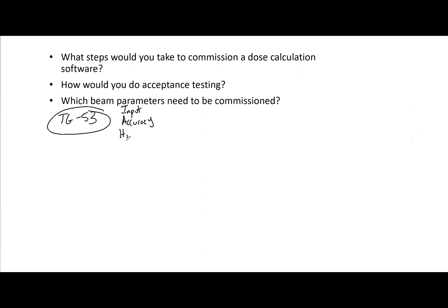You want to do this with water phantoms, and any type of anthropomorphic phantom is also good. Use a variety of plans — prostate, VMAT, SRS, SBRT, gating, any type of plans you could think of. You want to test all of those, and they are outlined in TG53. There's also much more in there, so read the task group and know what it says, and be prepared to talk in depth about how you commission a dose calculation algorithm.